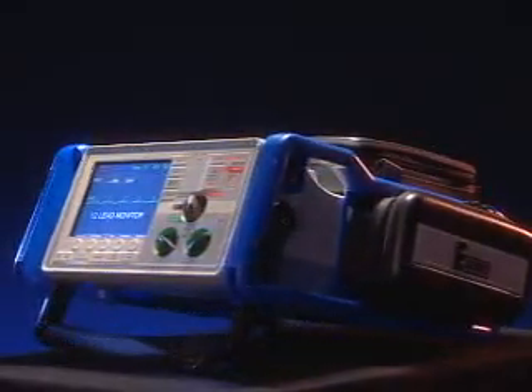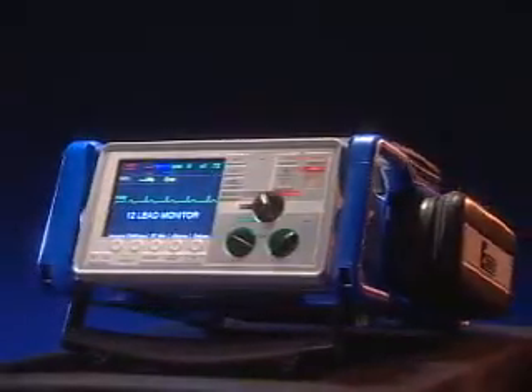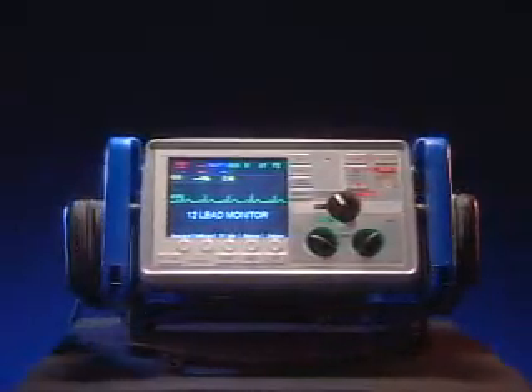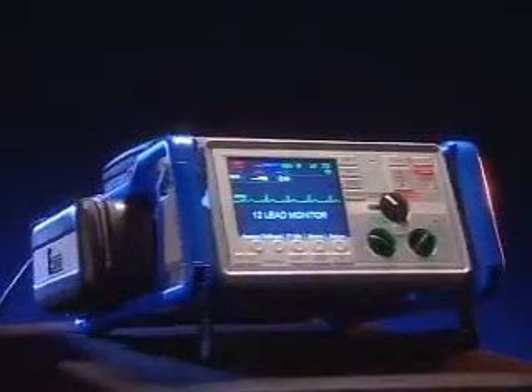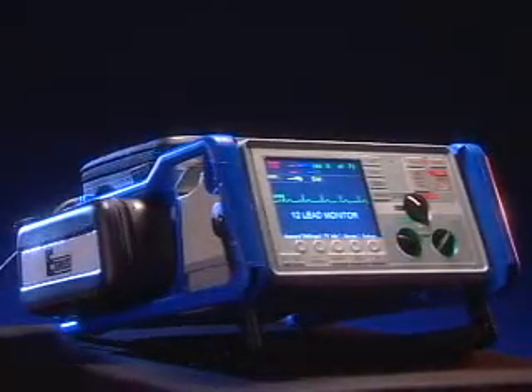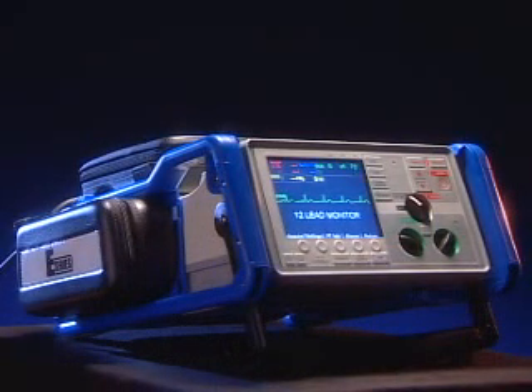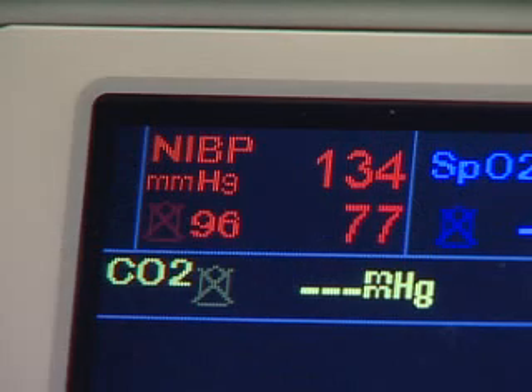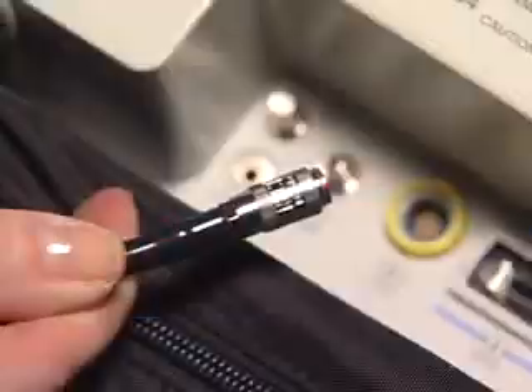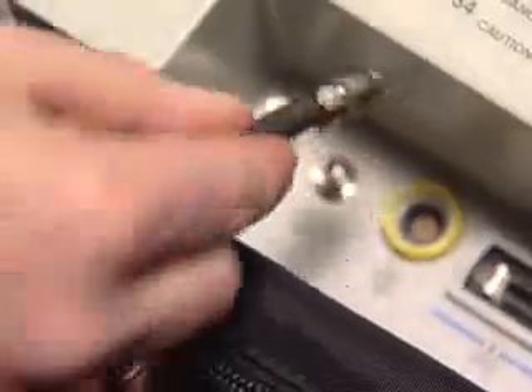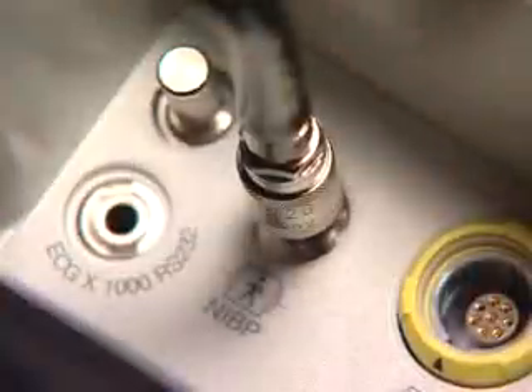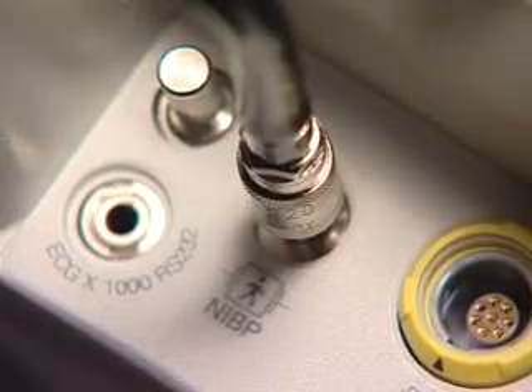The E-Series equipped with non-invasive blood pressure allows you to take a single blood pressure measurement, stat measurements automatically repeated over a 5-minute period, or automatic measurements at pre-selected intervals. Blood pressure information including your patient's systolic, diastolic, and mean blood pressure values is shown on the monitor in the NIBP display area. To take a non-invasive blood pressure measurement, connect the NIBP hose to the port on the rear of the unit and connect the BP cuff to the hose.